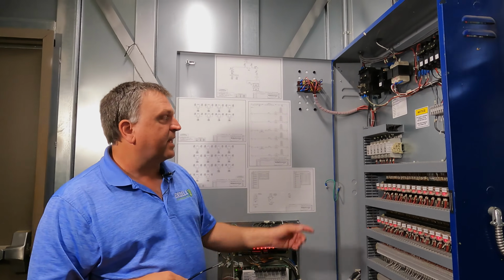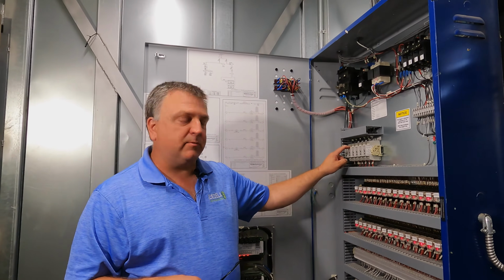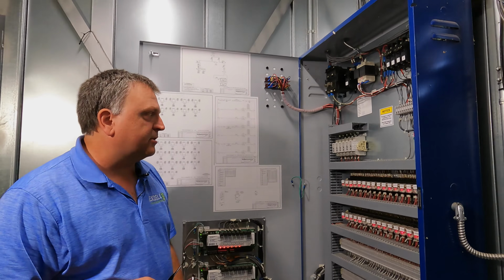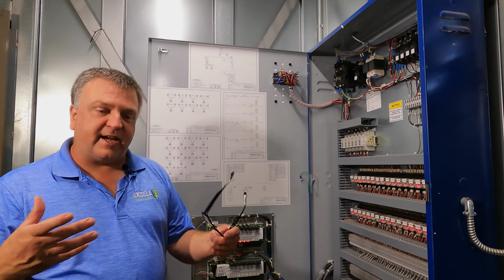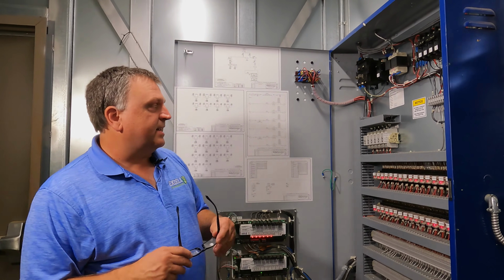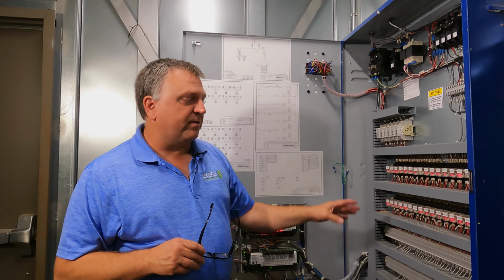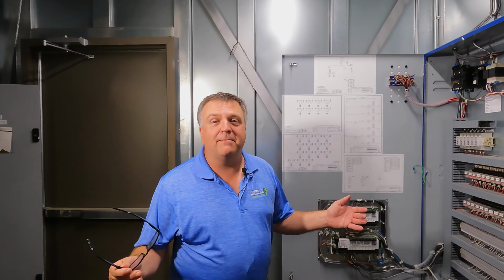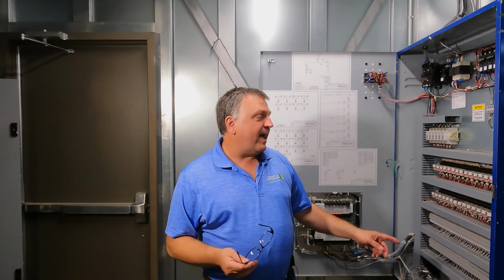That gives it enough time. Hey, we can energize our next set of relays. The next set of relays energizes, and then we bring those cases down to temp. The next set energizes, and so on and so forth until everything comes back on. Anything made by man is subject to fail. I have had these relays not energize before.